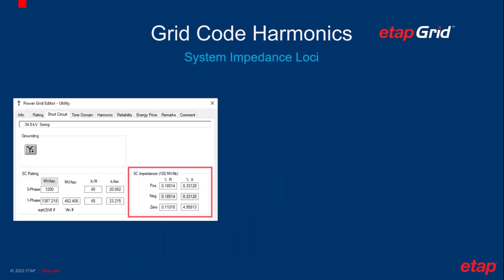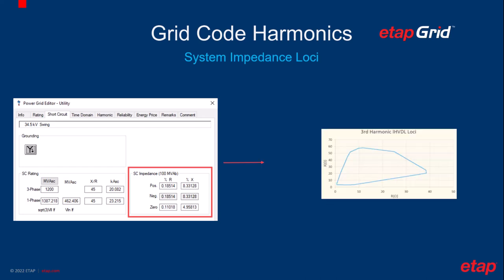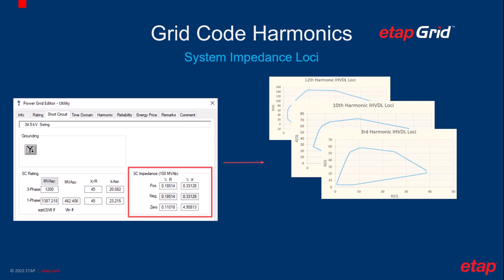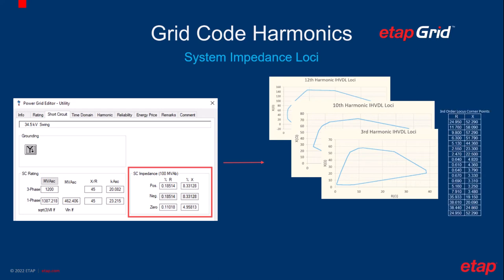Next, let's talk about the power grid impedance. In the traditional harmonic simulations, in each scenario, only one set of power grid short circuit impedance will be considered. In grid code harmonic studies, the TSO usually requires the applicant to consider various system operating conditions, contingencies, future expansions, etc. This is achieved by providing a set of diagrams of RX planes defining the range of possible system impedance under each harmonic order. The data is usually provided in the form of corner points of locus polygons.